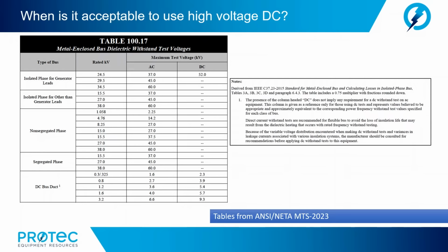All right, now let's take a look at table 100.17 of the NETA guides. This is for metal enclosed bus dielectric withstand test voltages. And again, we do see that AC is called out, but we do see the option for DC. But once again, we need to refer to the notes.